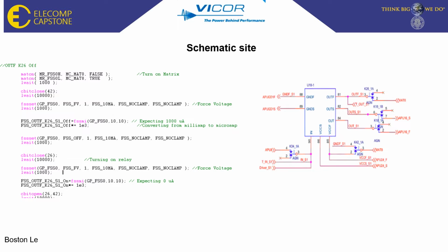On this slide, we take a closer look at the site of the PL69 main page. In this case, site 1, in the portion of the code corresponding to the test, voltage would be forced. We would first start the test by turning off matrix C-bit K42 and forcing the voltage to expect 1000 microamps. To get the value, we would start by closing C-bit K26, then open the relay and matrix back up to ensure the current reading is correct, getting 0 microamps, since no voltage should be coming through.